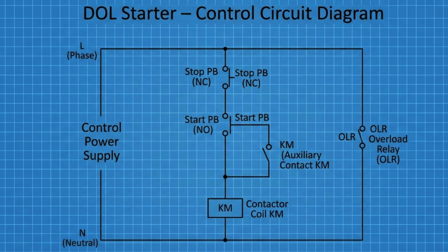On the screen, we are looking at the control circuit of a DOL starter. While the power circuit carries the high current to run the motor, the control circuit is responsible for controlling how the motor starts and stops safely. Let us understand the circuit step by step. The control circuit receives its supply from the control power source, which can be a single-phase supply or a control transformer depending on the system design.